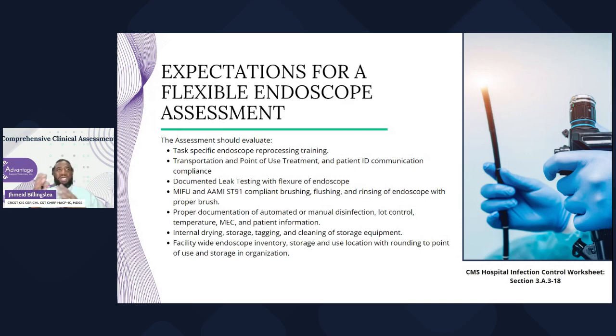Is the transportation and point of use treatment identified? Can we determine what's a delayed or enhanced reprocessing? Do we have documented leak testing with the flexure of the scope, right? So not just leak testing by manual, which we can make pass all the time. Do we have compliant brushing, flushing, and rinsing of the endoscope?